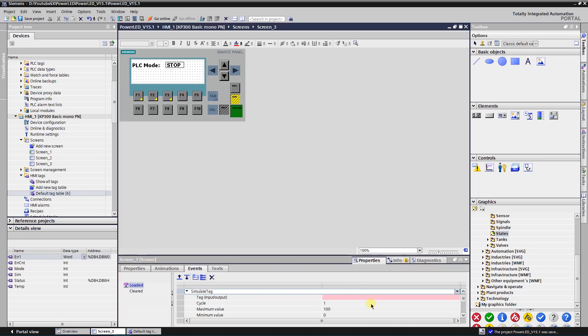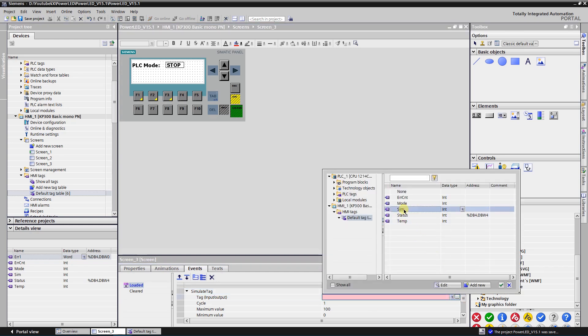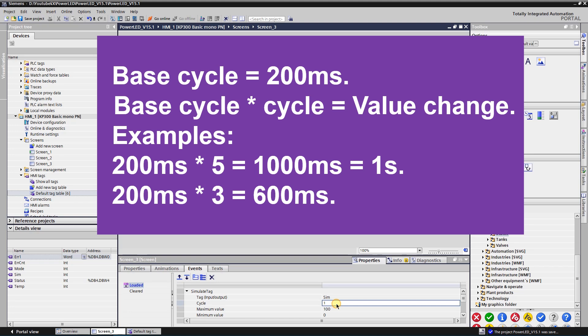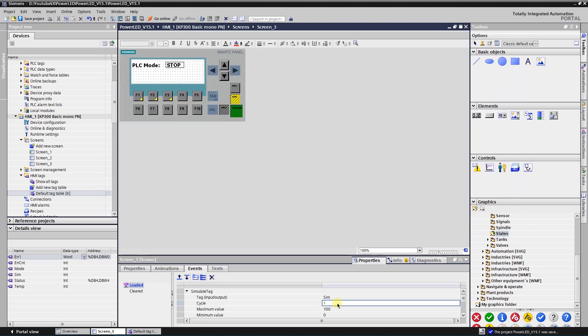Select the newly created integer type tag as the Tag parameter. Parameter Cycle is the factor by which the cycle is multiplied. One cycle is 200 milliseconds, so value 1 means that the tag value will be changed by the specified value at regular intervals of 200 milliseconds. Let's set here 5, so the tag value will be changed every 1 second. Parameter Maximum Value is the value that the tag can assume during simulation as maximum. The value of this parameter must be greater than the value of parameter Minimum Value.